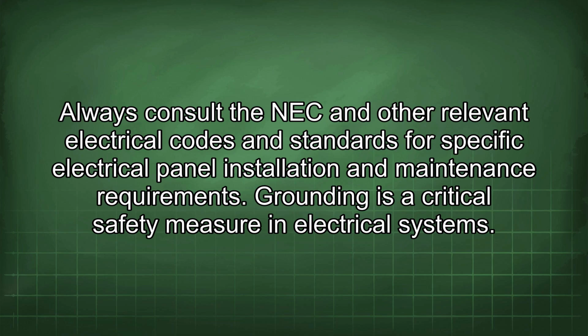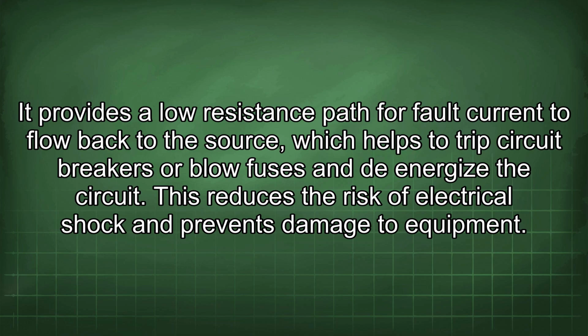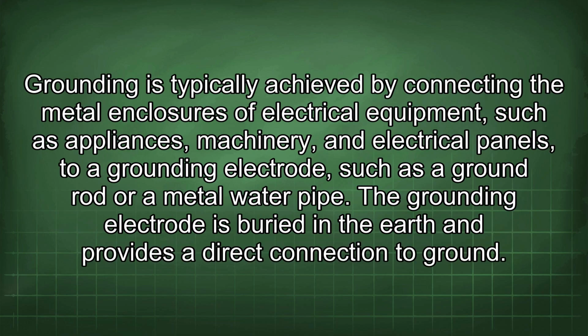Grounding is a critical safety measure in electrical systems. It provides a low resistance path for fault current to flow back to the source, which helps to trip circuit breakers or blow fuses and to de-energize the circuit. This reduces the risk of electrical shock and prevents damage to equipment. Grounding is typically achieved by connecting the metal enclosures of electrical equipment, such as appliances, machinery, and electrical panels, to a grounding electrode, such as a ground rod or a metal water pipe. The grounding electrode is buried in the earth and provides a direct connection to ground.